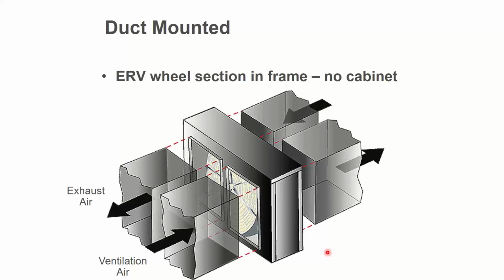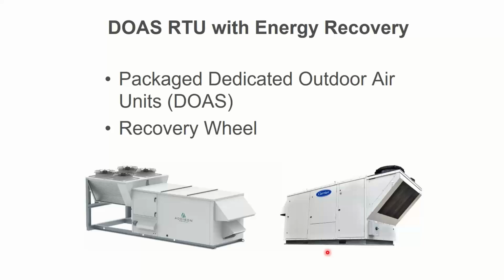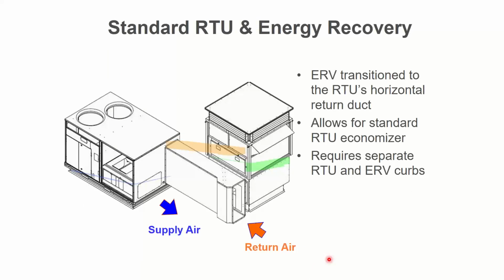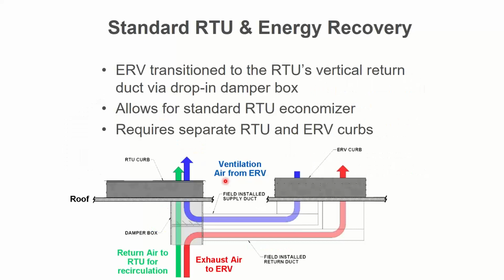If you have an existing air system, you could put the wheel-style ERV in the duct. The ducts have to be close to each other, but you can get a cartridge that slides in between the two ducts if you want to do that. You can get ERVs that are pre-built into packaged rooftop systems. That's an option as well. You could take a regular rooftop and an ERV and duct them together. You could have an ERV here on the right and a rooftop on the left and then duct them together below the roof line. You could do that.